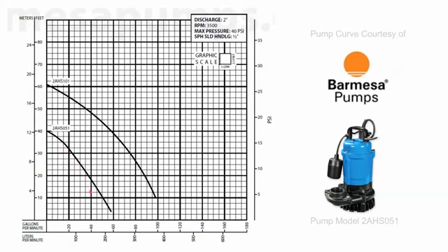And then you can also see on the flow side that the maximum flow rate of the half horsepower is roughly 56 gallons per minute, and of the 1 horsepower we've got roughly 95 gallons a minute, 96 gallons a minute, somewhere in there. So you can tell that the increase in work is a direct correlation of the flow and head performance of the particular pump.